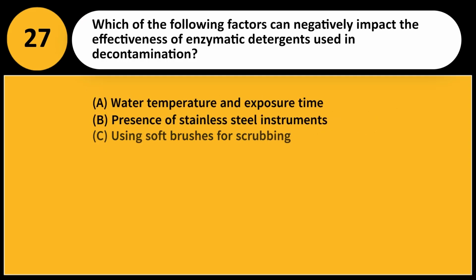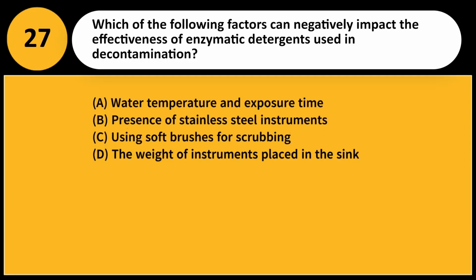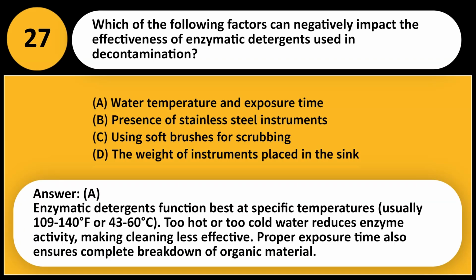Which of the following factors can negatively impact the effectiveness of enzymatic detergents used in decontamination? A. Water temperature and exposure time. B. Presence of stainless steel instruments. C. Using soft brushes for scrubbing. D. The weight of instruments placed in the sink. Answer: A. Enzymatic detergents function best at specific temperatures, usually 109 to 140 degrees Fahrenheit or 43 to 60 degrees Celsius. Too hot or too cold water reduces enzyme activity, making cleaning less effective. Proper exposure time also ensures complete breakdown of organic material.